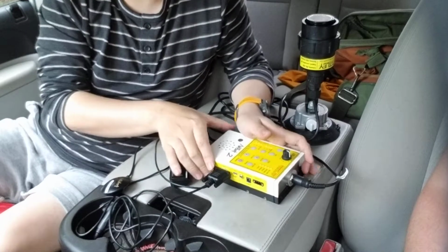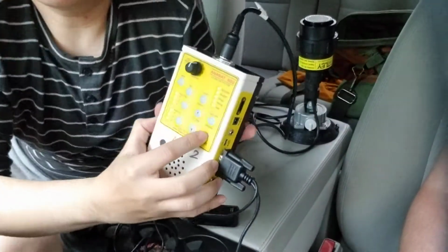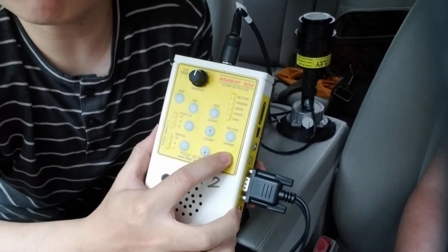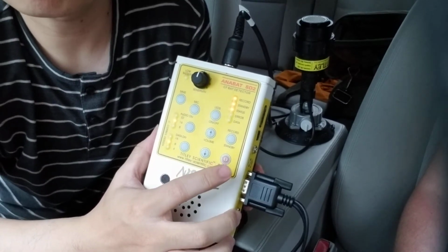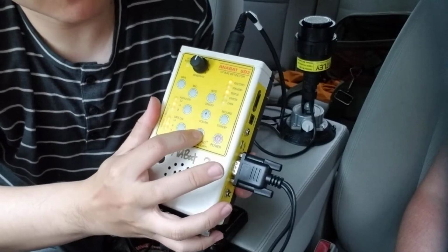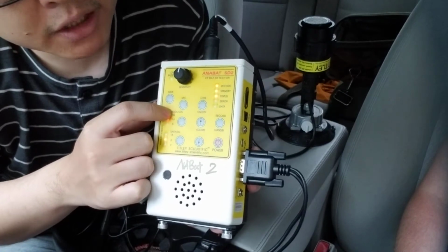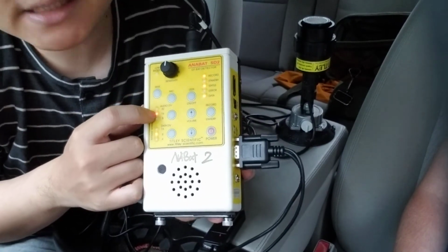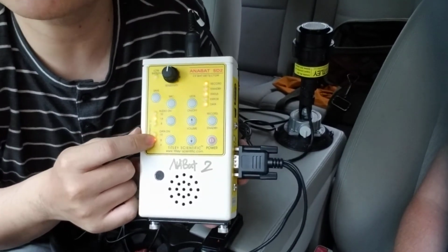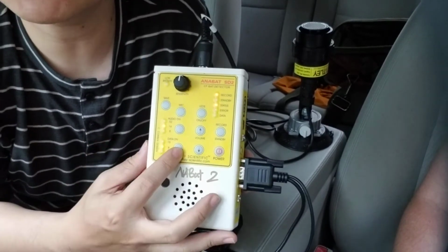And then once you have everything connected, you can turn the detector on. Once you turn the detector on, you get a little bit closer so you can see it. Once you press the power button, it will go on. You need to check a few things first. I need to turn down the volume. The first thing you need to check are those 2 things. You need to make sure the audio division here is 16, and data division, the second light, is next to 8, so we keep them. If you see the change, just press the button next to it to adjust.